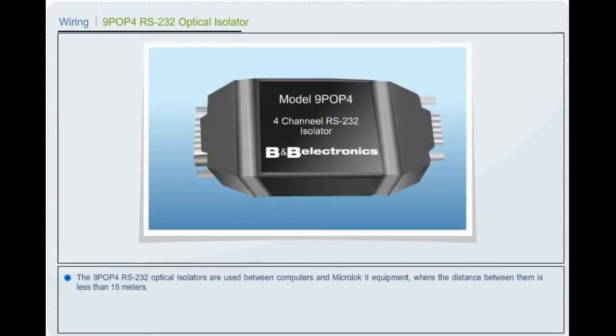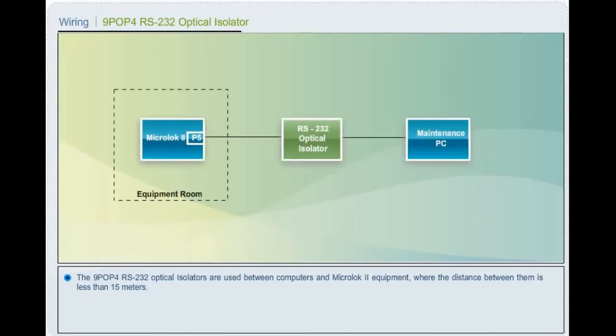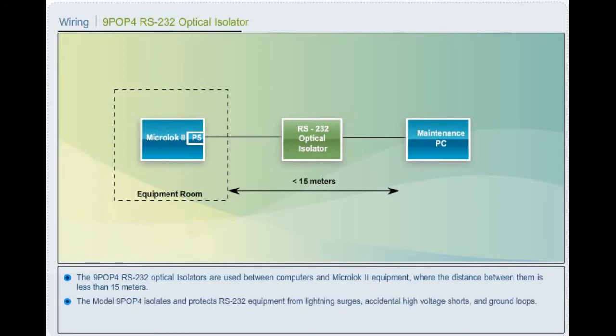Wiring. 9 POP4 RS-232 optical isolator. The 9 POP4 RS-232 optical isolators are used between computers and Microlok II equipment where the distance between them is less than 15 meters. The model 9 POP4 isolates and protects RS-232 equipment from lightning surges, accidental high-voltage shorts and ground loops. Normally, it is used between port 5 and maintenance PC.